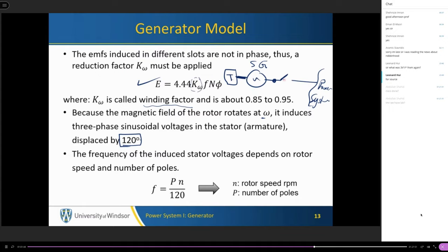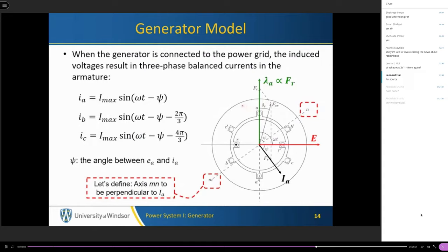What happens when we close the breaker connecting the synchronous generator to the power system, or the breaker that connects the generator to the load? In this case, the generator will supply current to the load, and this current will flow through the stator winding. This is the stator winding, three phase, IA, B, and C.